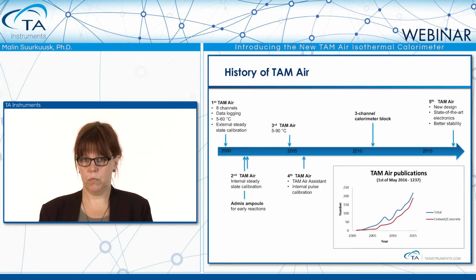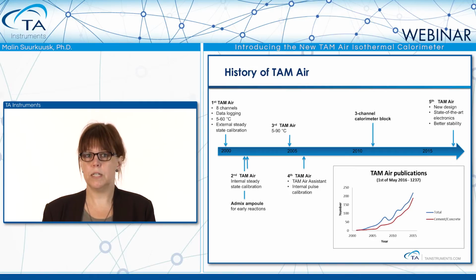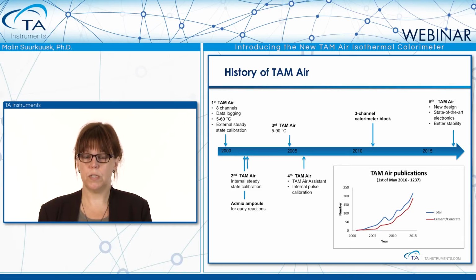2 years later, we introduced a second TAM Air, where we just moved the calibration procedure to an internal one. At the same time, we also introduced what we call the admix ampule, which allows you to add and mix sample inside the calorimeter to not miss the initial reaction. 2005, the third generation TAM Air was introduced, where we increased the temperature range up to 90 degrees. And 2006, there was a new software, TAM Air Assistant, that both performs the experiment and can help you in analyzing the data. Also a new calibration procedure that we use still today.